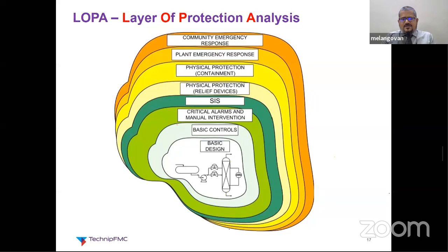I have selected the correct material of construction compatible with the diesel, and I have set it to the correct design pressure to overcome any overfilling scenario. I have selected the distribution pump to minimize leaks from the seal. I have selected a double mechanical seal distribution pump. So these are all the basic design features which I have incorporated to prevent any accidents.